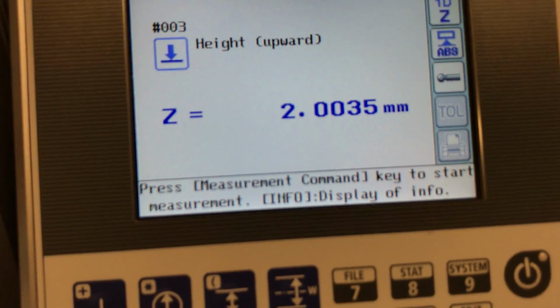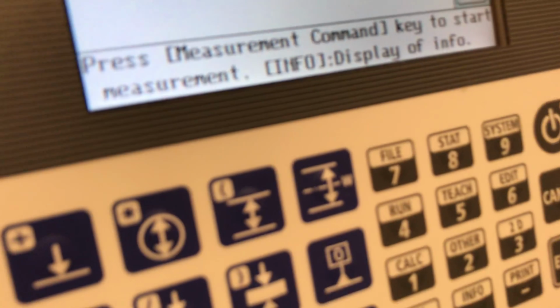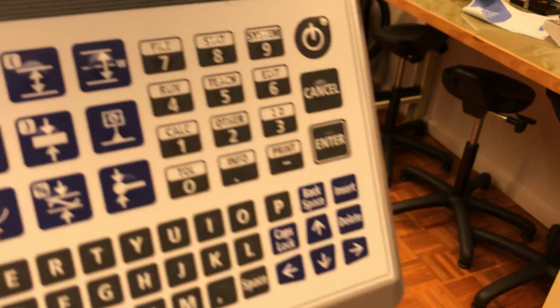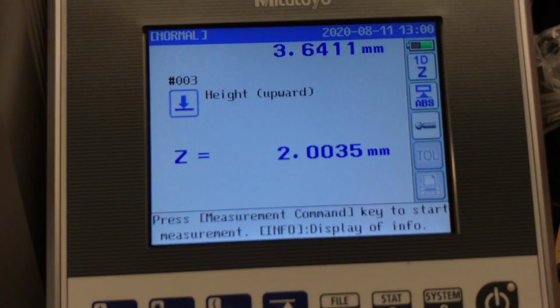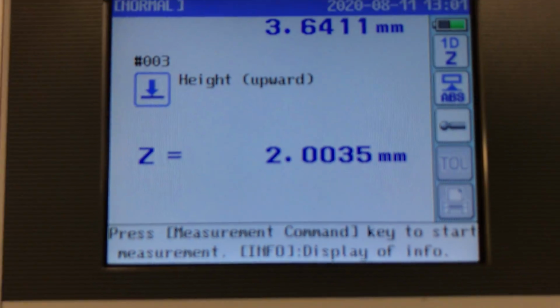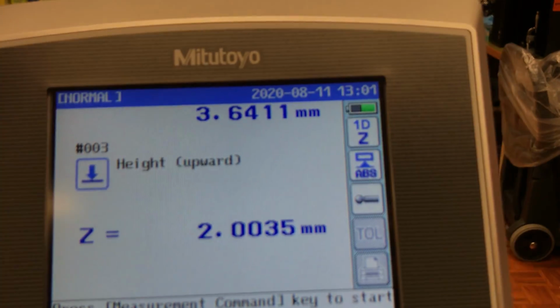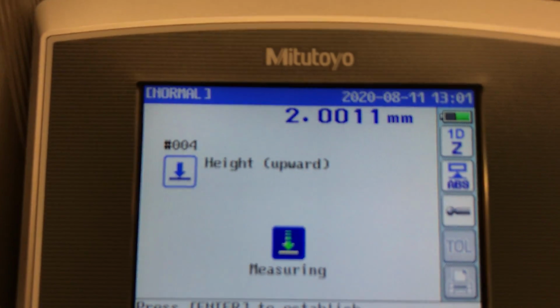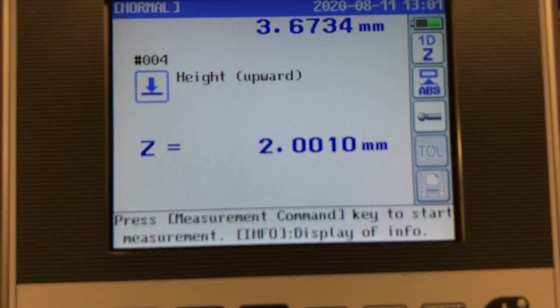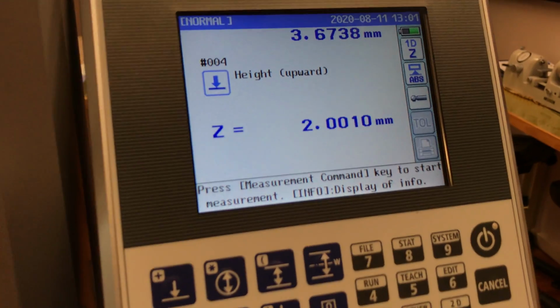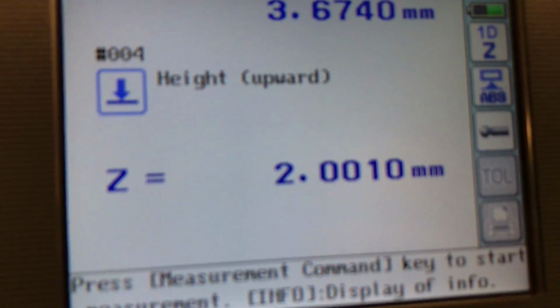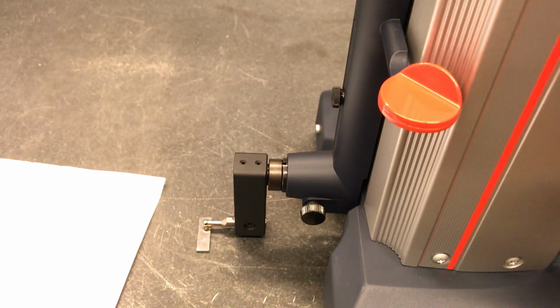Okay, now you can see that the error has been dropped. Now we're reading 2.0035. So this is a good indication that what's happening is not the machine itself, but the table having some error. We need to take about 5 readings on average and fill the table attached to your work. In this position, it tells me exactly that the height is 2.001, and this is the actual height.